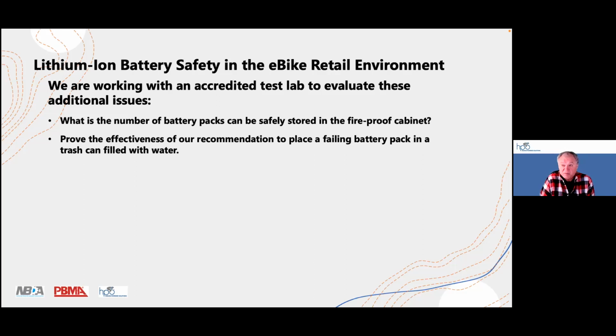A battery pack, for all extents and purposes, is watertight. That water tightness will be compromised by a cell in thermal runaway, because it will melt plastic quite quickly, and it will melt aluminum too, in a relatively short period of time. I've got photographs that prove that. The idea is that once that containment is breached, water will flood the compartment, cool the adjacent cells, and stop the propagation. That's the rationale behind this recommendation, but we need to prove it out.